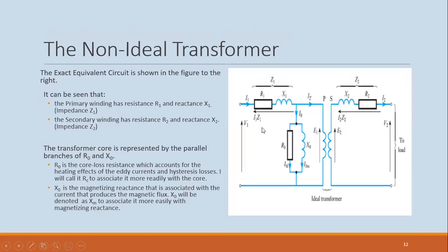Now notice there is an I0 here too, called the no load current. This no load current exists whether there's load on the transformer or not. Once the transformer is energized, a current will flow to supply the no load power loss. It will supply the core loss power and the magnetizing current that creates the magnetic flux, so it has two components: one that supplies the eddy current and hysteresis losses, and the other that provides the magnetizing flux.